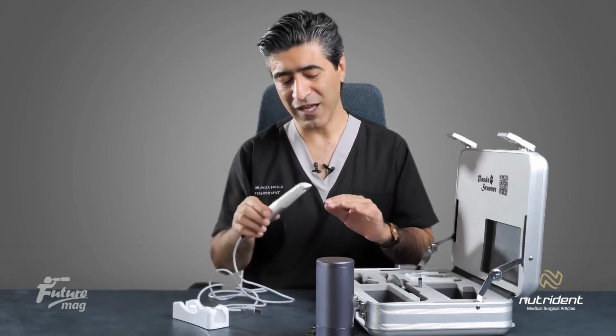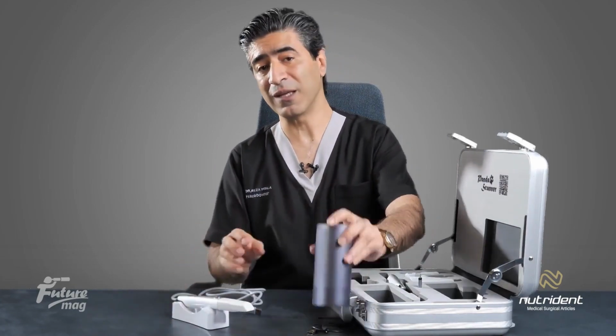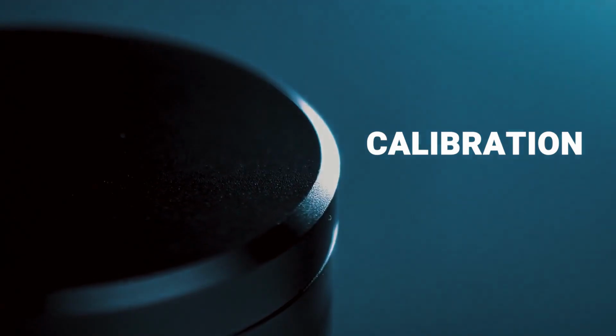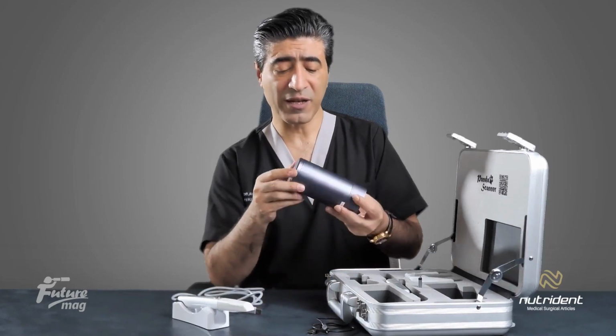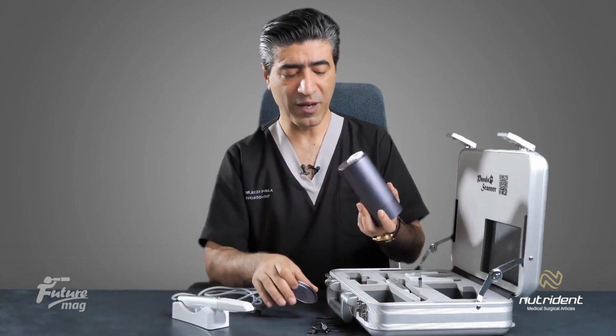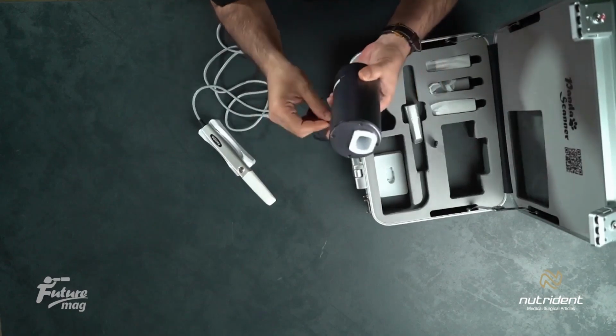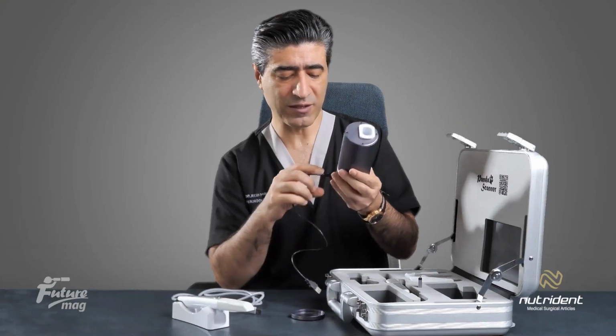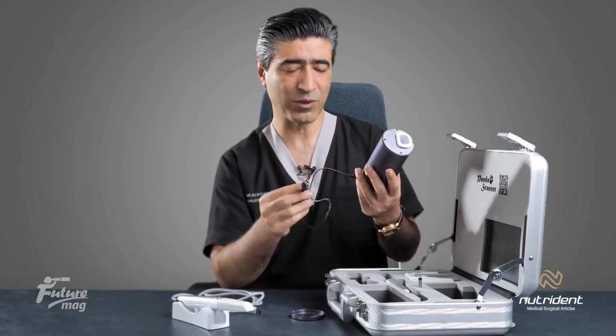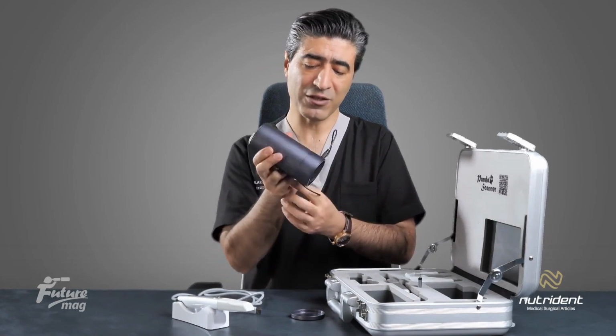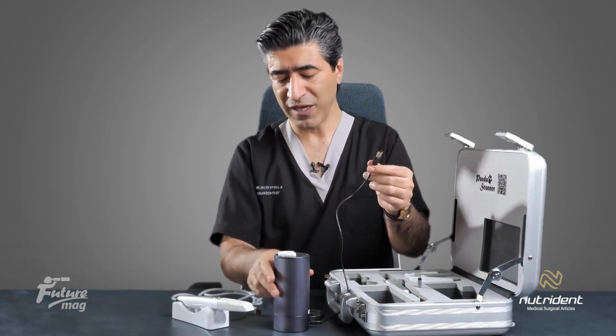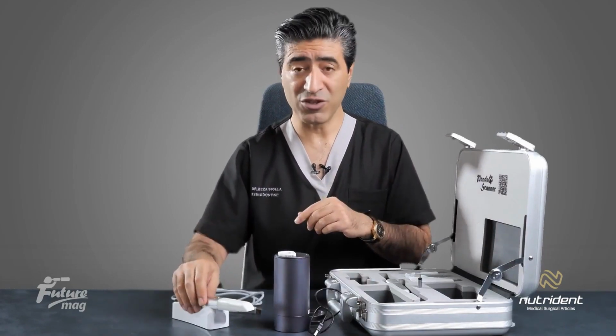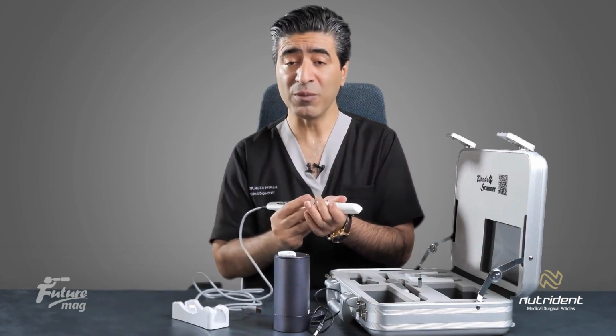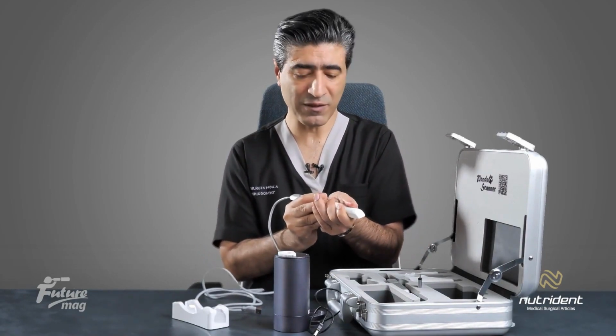But before we finalize the hardware, let's talk about the calibration part. Well, the calibration piece is such a piece that you need a power source to work with this piece. This power is very easily supplied from a USB connection, and you can easily perform this calibration with the same laptop you have. This piece is connected to the system's USB port, and the scanner is placed on this product while it is turned on for calibration. This piece performs both 3D calibration and color calibration for you.